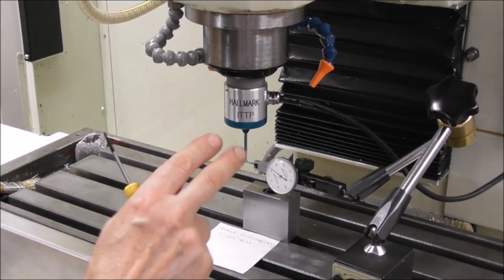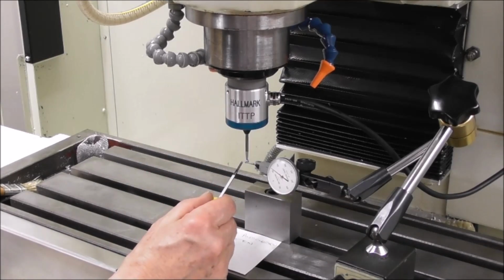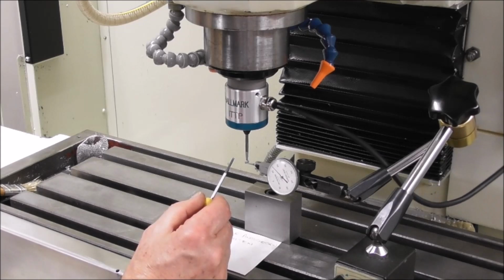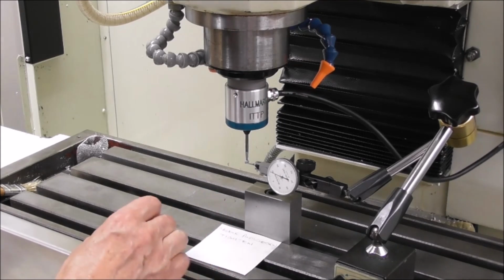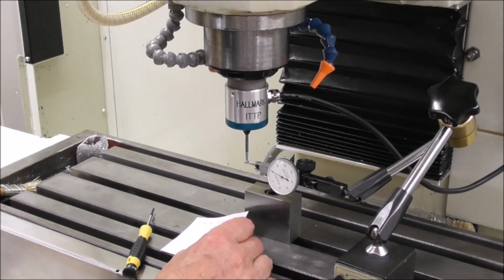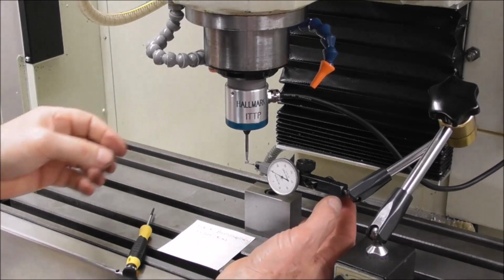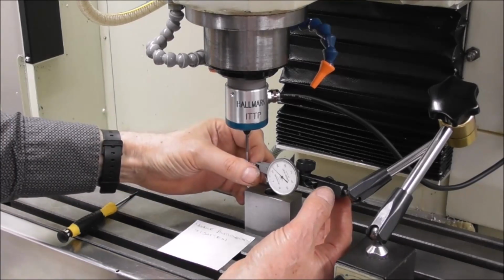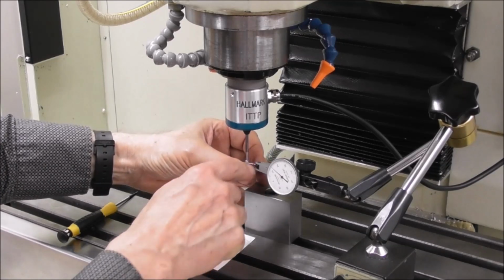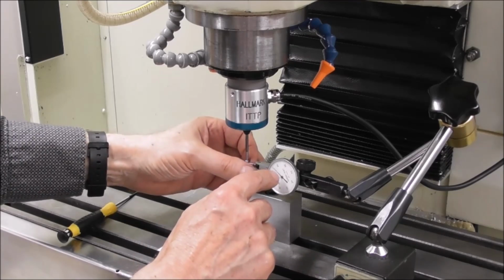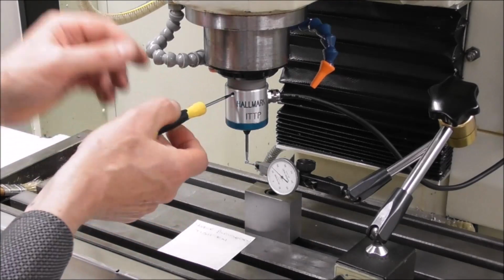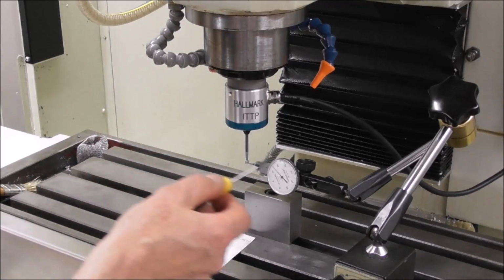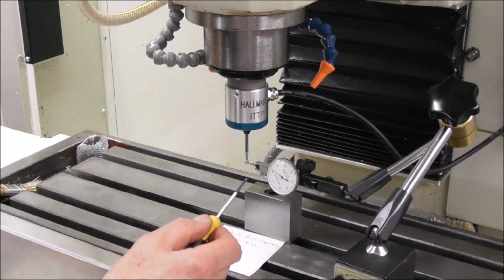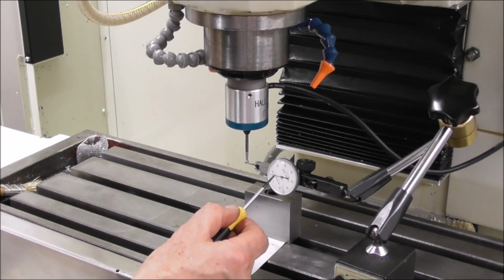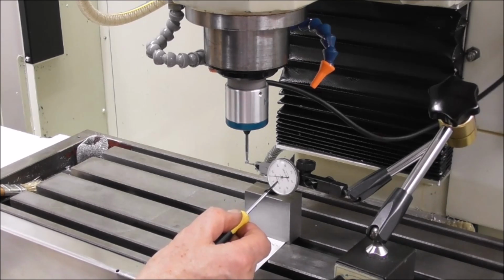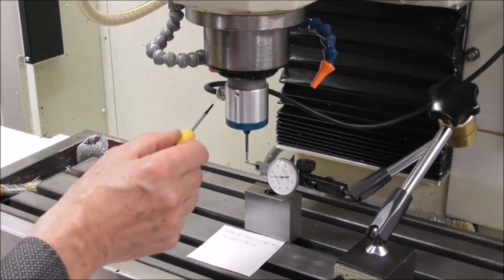Okay, let's go through actually setting the probe concentric. So we've got a light finger indicator touching the stylus tip, and when we rotate it we can see that it's not concentric. So it's really helpful if you're procedural about this and that you really understand what you're doing, otherwise you can be chasing your tail around in circles for ages. So have a look at your dial indicator, work out which way the stylus of the indicator moves, which way the needle moves, and what the effect is of tightening these set screws. And so when you've worked it out, in my case, if I rotate the probe and the needle of the indicator goes anti-clockwise, that's that way, then the set screw to the front needs to be tightened.